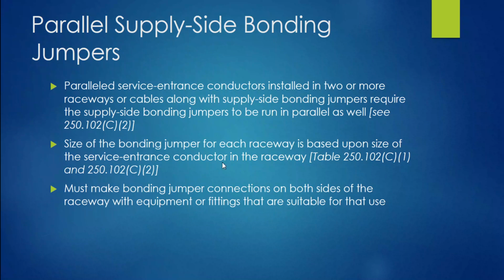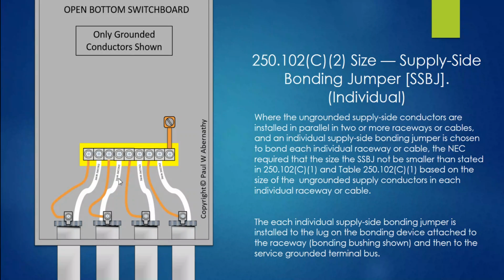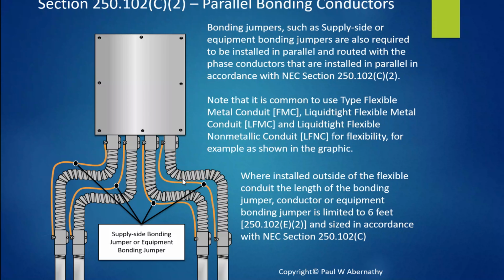Okay. Now, let's talk about parallel supply side bonding jumper, because that is talked about in 250.102(C)(2) in the actual language. All right, it's talking about that. So when you have parallel service entrance conductors installed in two or more raceways or cables, along with supply side bonding jumpers, it requires the supply side bonding jumpers to be run in parallel as well. All right, so this would be an example of that. Okay, but if it's in a cable assembly and you're using a cable assembly that is allowed to be run with service entrance conductors, then you might run into something like this. Whereas here you have this, as long as it's not over 6 feet, and this is all covered within the National Electrical Code in 250.102.